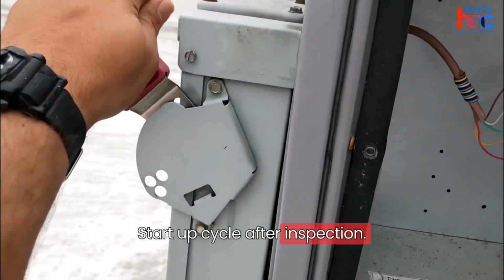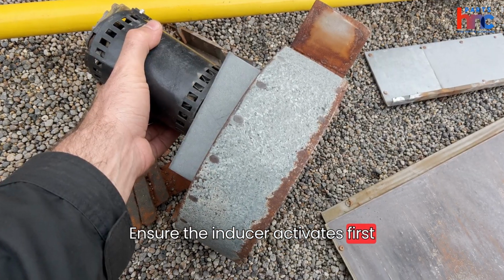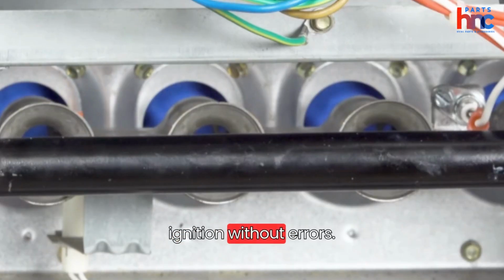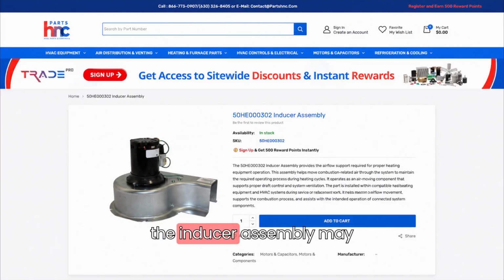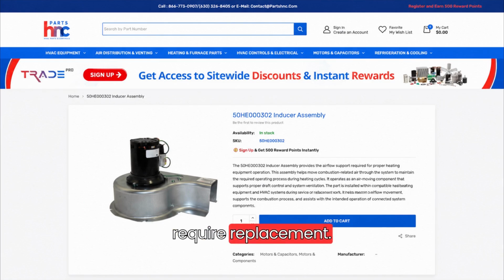Run a full startup cycle after inspection. Ensure the inducer activates first and the unit completes ignition without errors. If issues continue, the inducer assembly may require replacement.